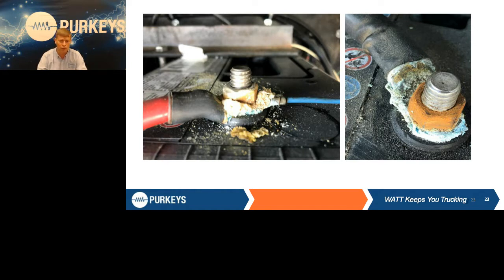One other thing is when you're doing your battery connections, you should always be as opposite as possible. If you have 2 batteries, put positive on one and negative on the other, so you're charging across those battery packs. Same thing with whatever your load is, whether it's a truck with big cables going to the starter, or a liftgate with cables going to the pump motor, always put them on opposite batteries. You'll get much better charging across the entire pack and a more even discharge across the pack by doing that. So it's not just, hey here's a positive, throw a cable on it. For optimal performance, you do want to do all those things.